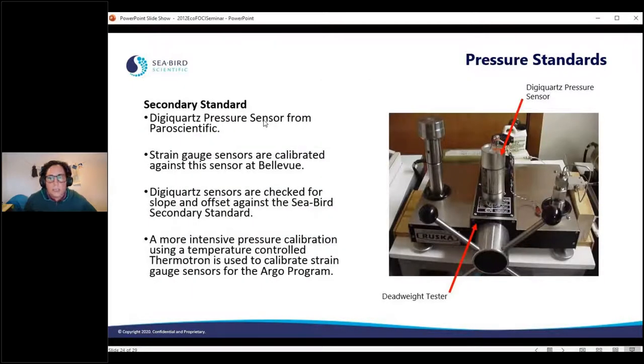And then the last thing is pressure standards. Like I mentioned, for those Digiquartz sensors, we can't actually calibrate them because we just don't have that capability - it's a really big capability to get to that accuracy. So we actually use a Digiquartz pressure sensor to calibrate a lot of our strain gauge sensors, and that goes back and they're able to do that calibration as well. We use that for calibrating our strain gauge sensors.